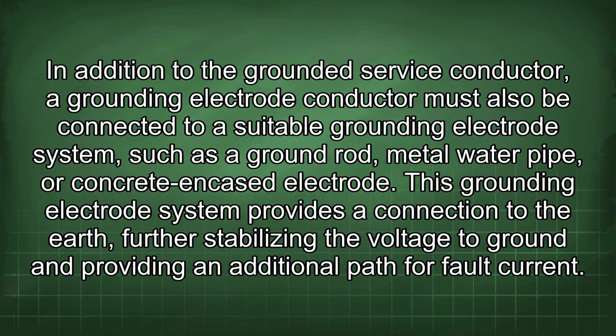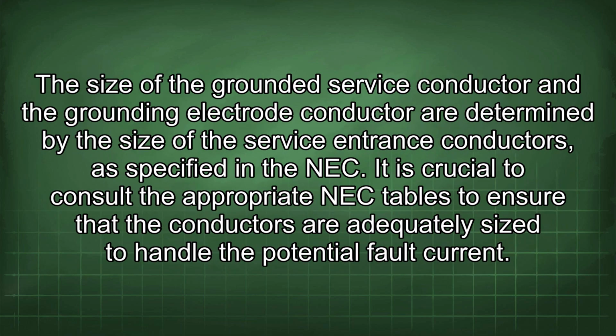In addition to the grounded service conductor, a grounding electrode conductor must also be connected to a suitable grounding electrode system, such as a ground rod, metal water pipe, or concrete encased electrode. This grounding electrode system provides a connection to the earth, further stabilizing the voltage to ground and providing an additional path for fault current. The size of the grounded service conductor and the grounding electrode conductor are determined by the size of the service entrance conductors as specified in the NEC.